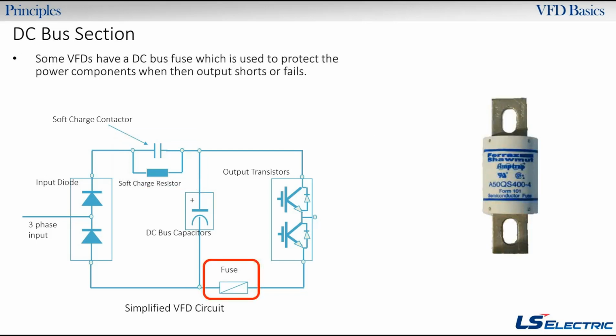Also, most drives are going to have fuses in them too. The fuse is going to be more towards the output side. So here we have output transistors, which we haven't talked about yet, but we're going to talk about them on the next slide. Then you have this fuse here. If anything happens within the motor, let's say the motor shorts out, these transistors could get damaged. And then that could go back and damage the capacitors and the rest of it. But there's this fuse here that separates the output from the rest of the drive. So if there's ever a short on the output, the fuse clears, and then the rest of the drive is protected. That way you only have to replace a few components instead of replacing a whole drive or every component under there.